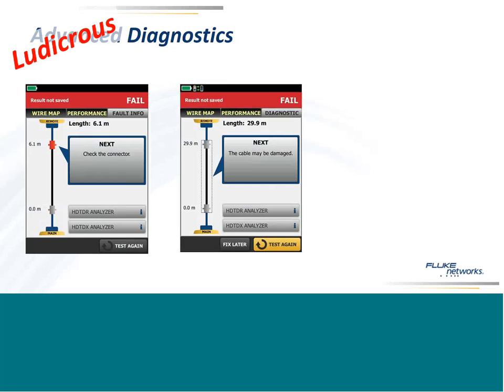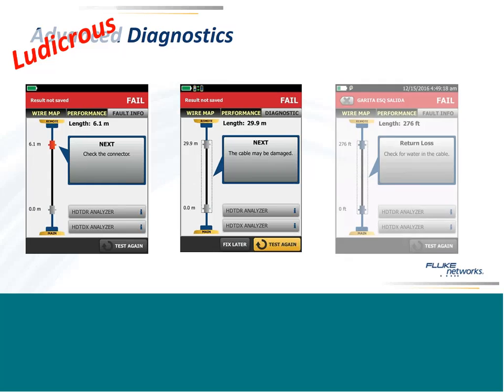Another one is that it can tell if the cable's damaged or if the cable's actually bad quality. I mentioned the copper-clad aluminum and all that. It'll tell you exactly which cable and where in the cable. In this case it says it's not a spot in the cable, it's the whole cable that has a problem. A lot of this is because we've worked with tens of thousands of customers who've had problems, and we now know what they look like electronically, and so we can put it into this simple display. But this is my favorite.